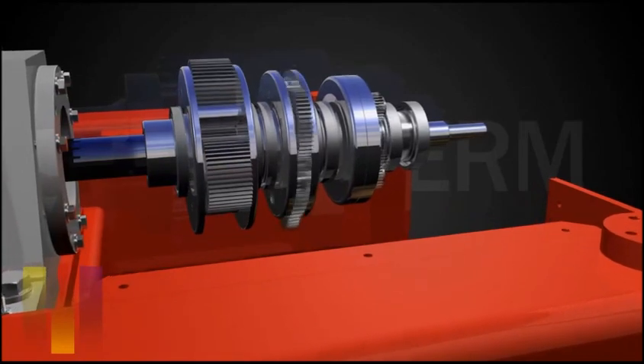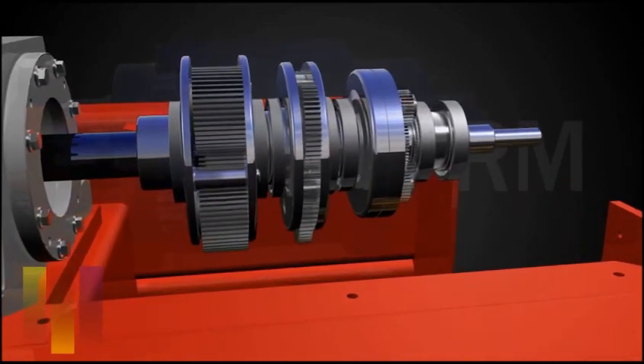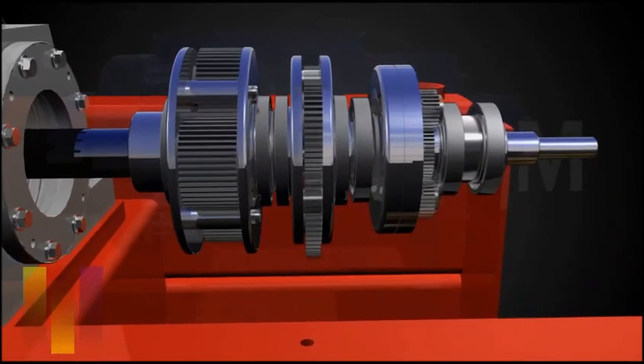Inherent is also the large overhang load of the heavy gearbox, causing additional stress on the main bearings and other mechanical centrifuge components.